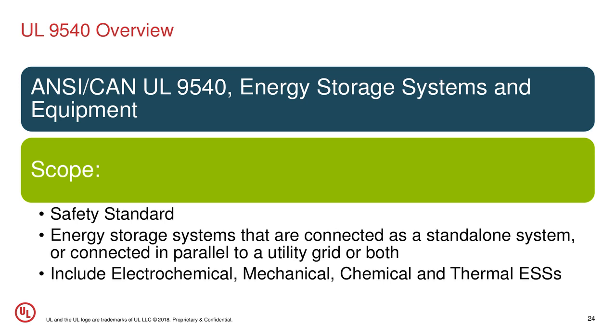So just an overview of UL 9540. It's an ANSI Canadian standard, a national standard for both the US and Canada. Energy Storage Systems and Equipment is the title, and it's a safety standard. It's for energy storage systems that can be connected as a standalone system, or in parallel with a utility, or both—they call it multi-mode, I guess. There was a question I noticed off to the side.